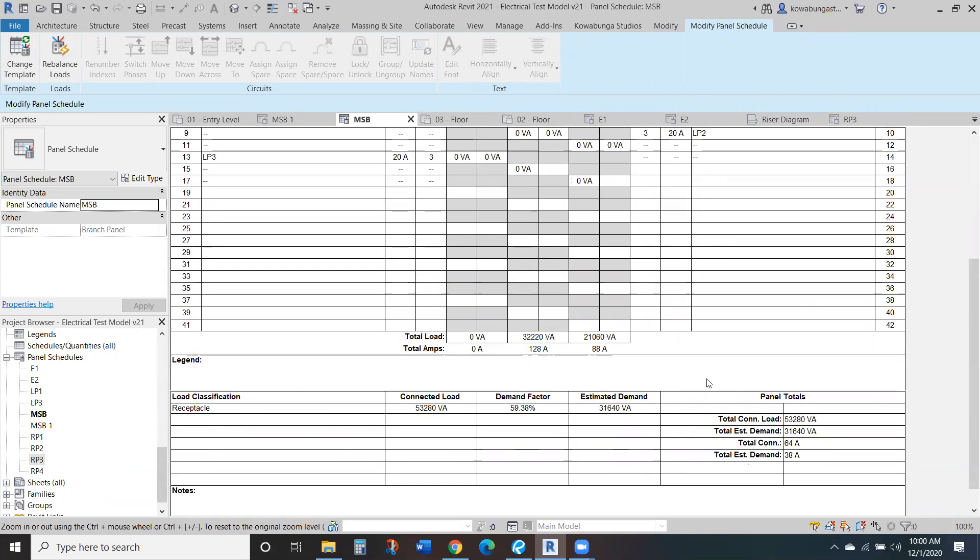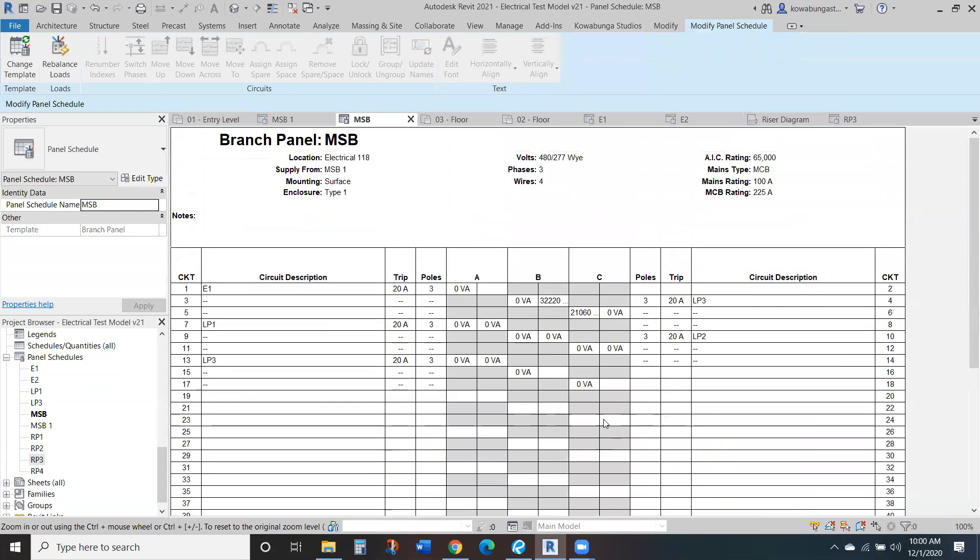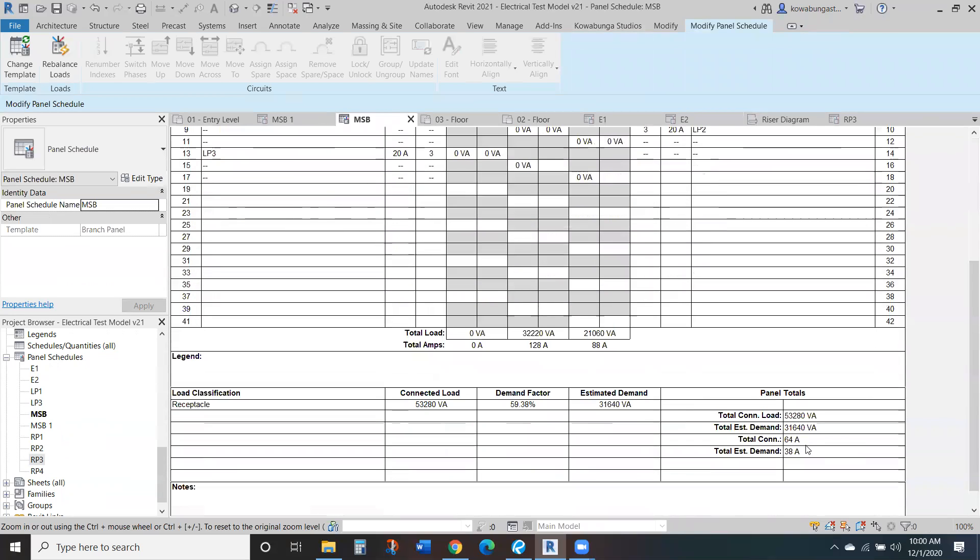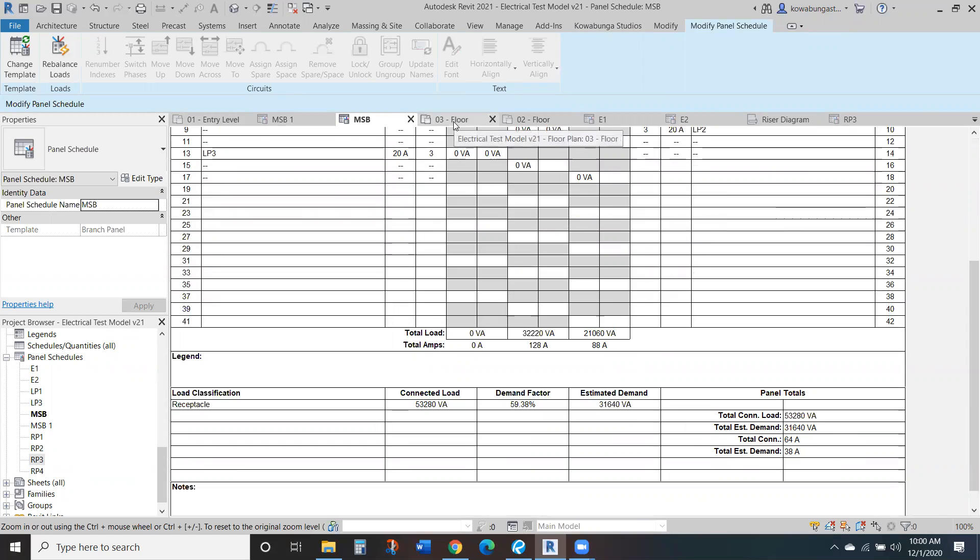But again, load classification, your demand factor, everything like that. Total connected, again, this would be across the phases, not a peak phase demand is where your total connected is. So it's taking that over three to give you the total connected loads. So that's how Revit is doing it. Again, if you actually had balanced it out, it would be 64. So it's a total connected balanced load, not unbalanced max phase.